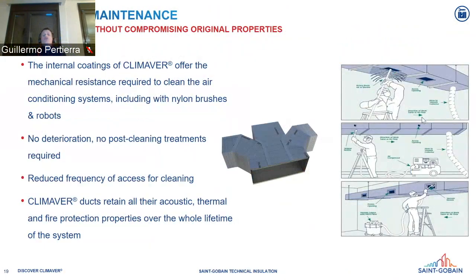Another good reason to choose CLIMAVER is that it minimizes maintenance. It's very easy to clean, and the internal facings of the whole range are proven and tested to resist mechanical cleaning. We test the product, cleaning it with nylon brushes or other kinds of brushes with air pressure, and afterward we make another test to verify that the performance stays the same.